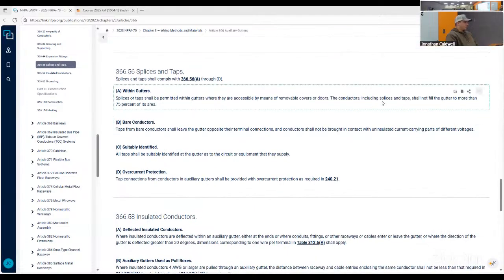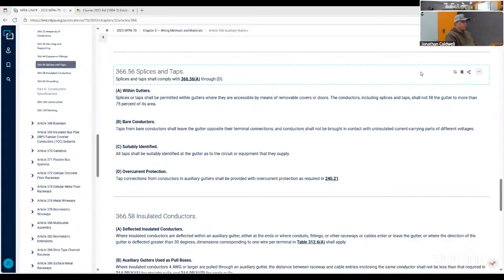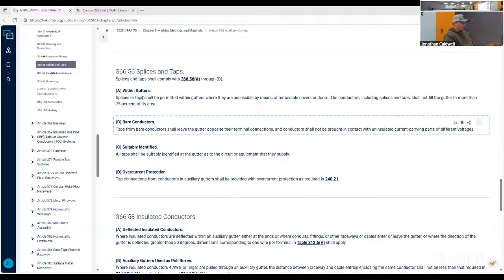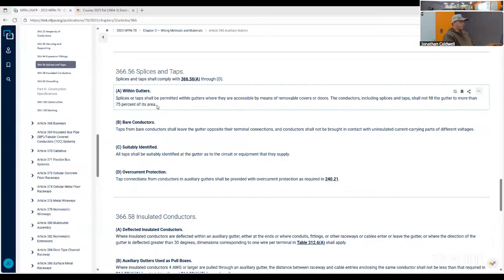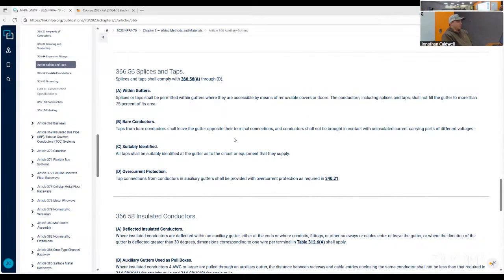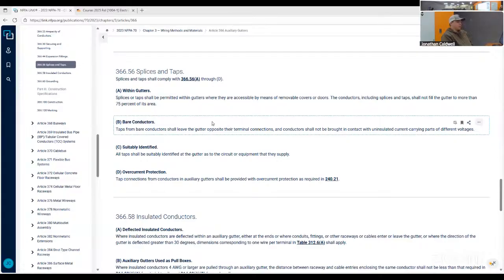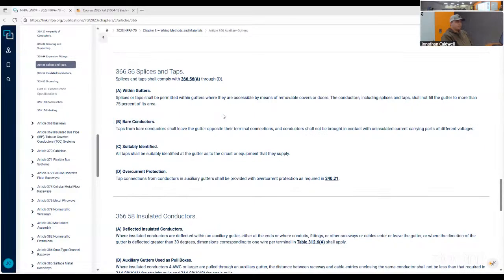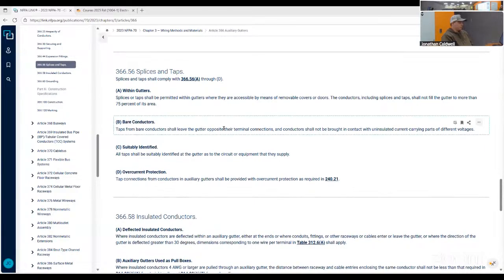Within gutters, splices or taps shall be permitted where they are accessible by means of removable covers or doors. The conductors, including splices and taps, shall not fill the gutter to more than 75% of its area. So that goes for using distribution blocks as well. The biggest part with distribution blocks is making sure you have enough depth on your gutters. Does it make it a lot cleaner than using Polaris lugs and split bolts and all that? Yeah, it does.